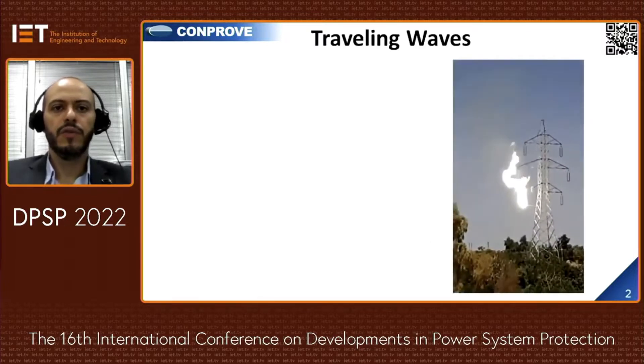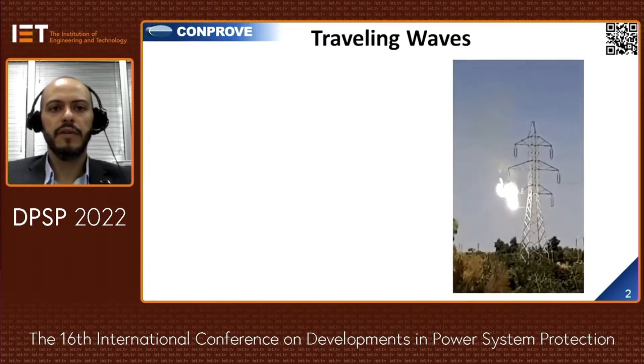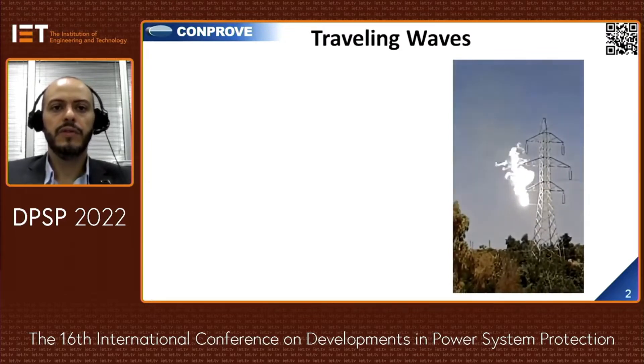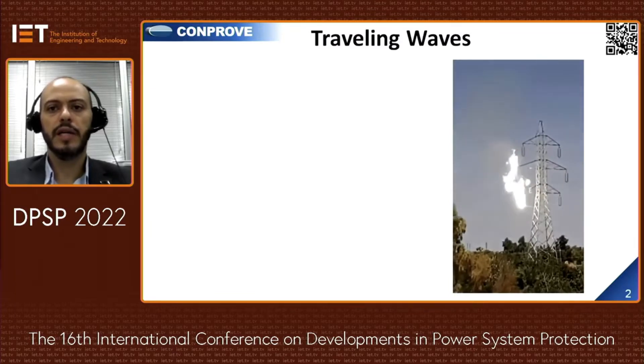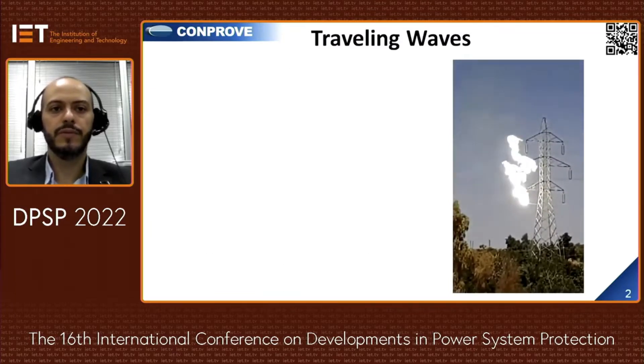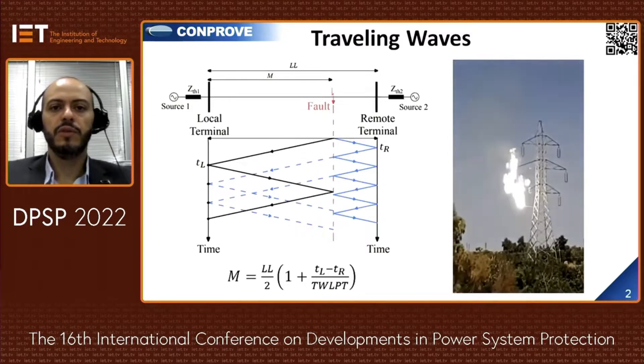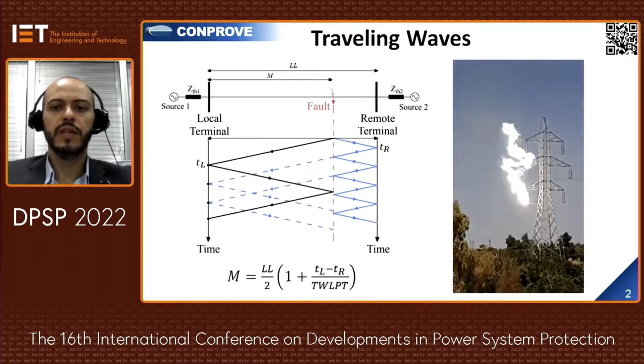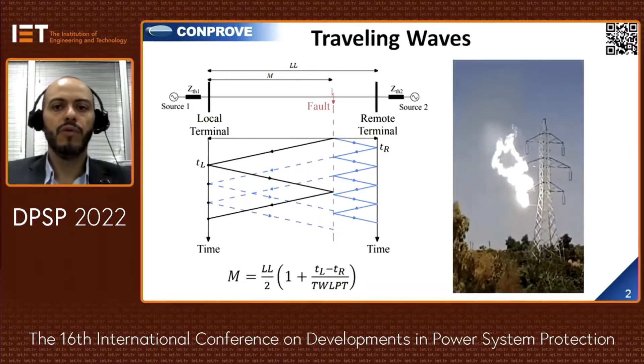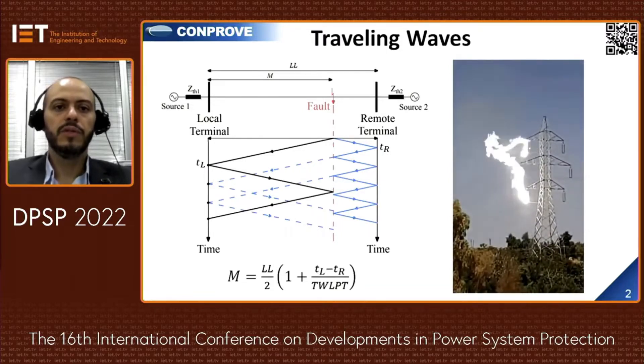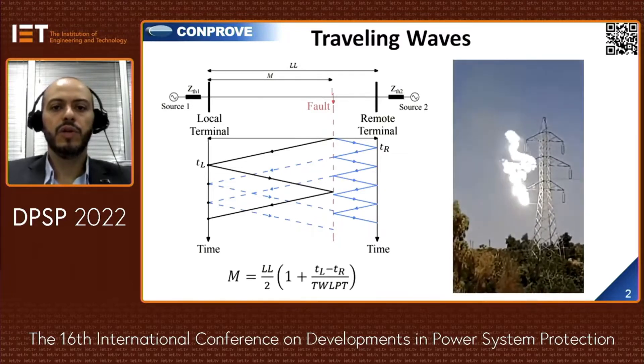First of all, the power system must be better and smarter every day, and traveling waves technology can help this occur by enabling faster trip and high-accuracy fault location. The fault on the transmission line will generate transient waves that propagate at close-to-light speed to both ends; measuring the TW arrival time, it is possible to calculate the fault location.